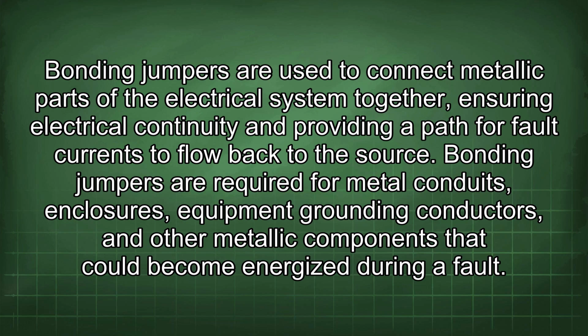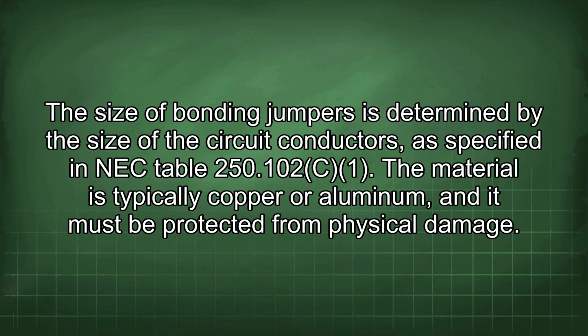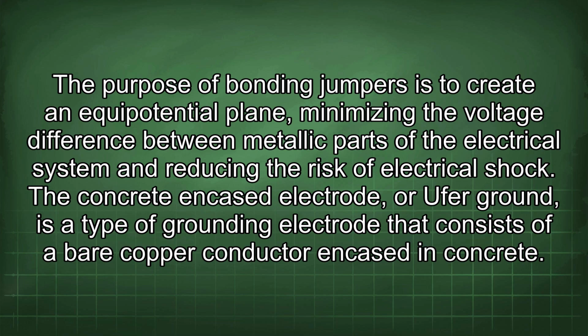Bonding jumpers are used to connect metallic parts of the electrical system together, ensuring electrical continuity and providing a path for fault currents to flow back to the source. Bonding jumpers are required for metal conduits, enclosures, equipment grounding conductors, and other metallic components that could become energized during a fault. The size of bonding jumpers is determined by the size of the circuit conductors, as specified in NEC Table 250.102. The material is typically copper or aluminum, and it must be protected from physical damage. The purpose of bonding jumpers is to create an equipotential plane, minimizing the voltage difference between metallic parts of the electrical system and reducing the risk of electrical shock.